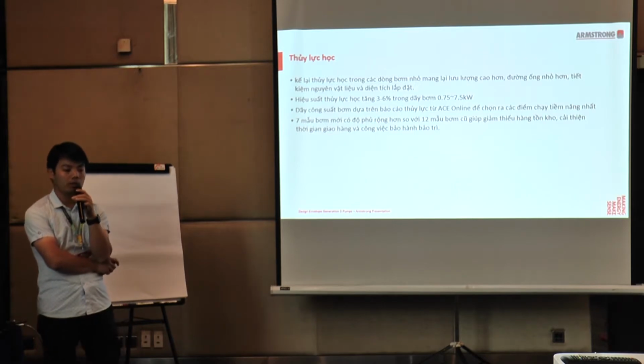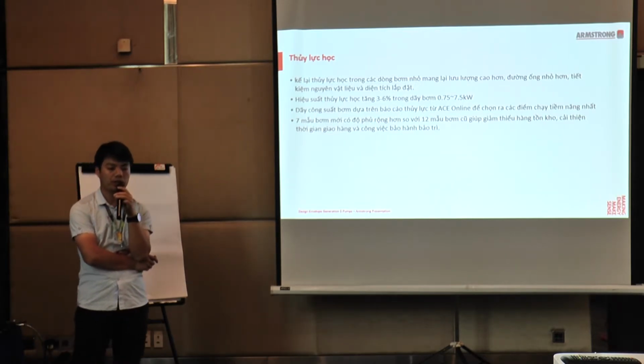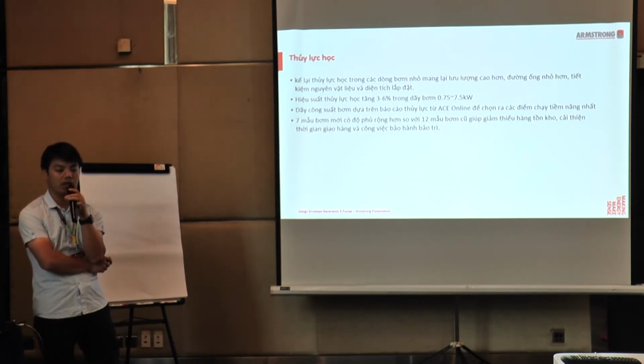And for the hydraulic design, we have redesigned the hydraulics, and thus we can achieve a small size and create the highest flow rate with the smallest quiet nozzles. We can also improve the hydraulic efficiencies by 3 to 6% points in the below 10 horsepower range. And for the pump coverage, the power rate range is based on the analytics of our current online selection tools. And here are the 7 new pump models with broad coverage, compared with our previous 12 models.